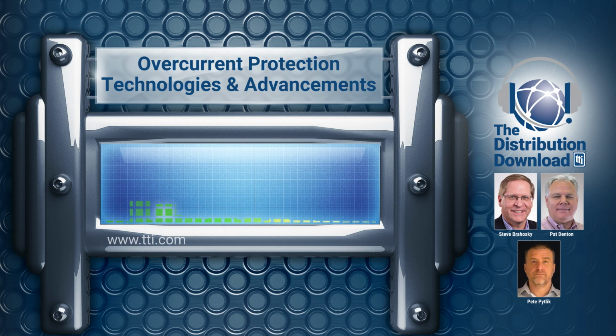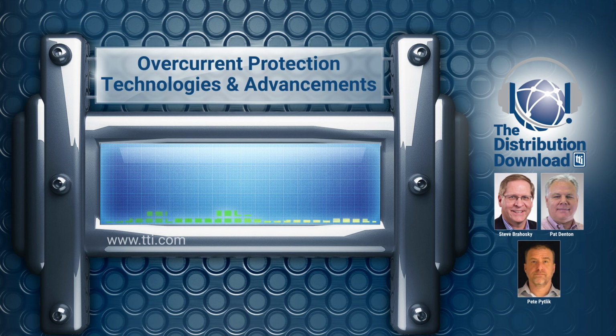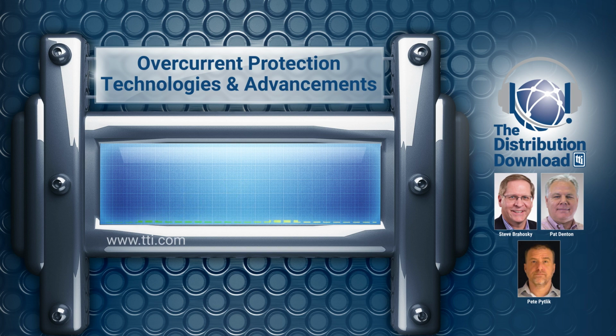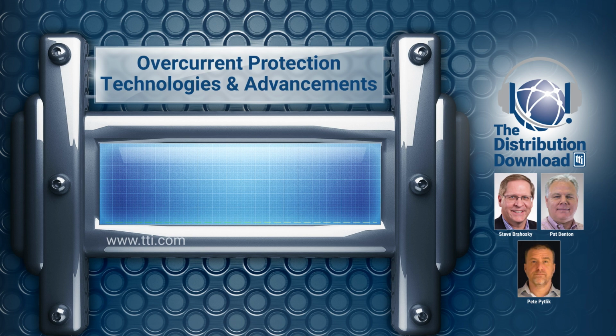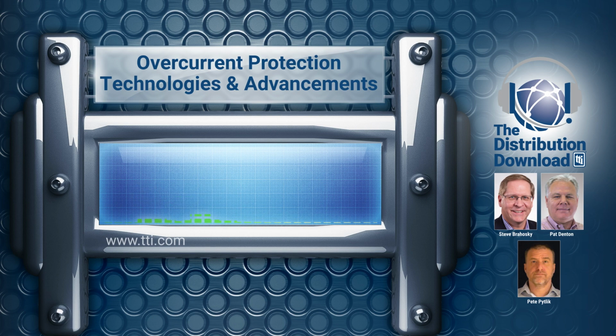Thanks, Pete. This first session, we're focusing on overcurrent. Can you give us a brief overview of the Littelfuse overcurrent portfolio and the reasons we need overcurrent protection? Sure, great question. Maybe we'll start out with, what are the reasons for overcurrent protection? Really, the purpose of an overcurrent protection device is to be an intentional weak link in the circuit. So what are we looking really to protect against? Fires, also any type of injury that may occur. The purpose is also to safeguard any other components in the application. So it's really to be the first level of protection to protect the circuit.